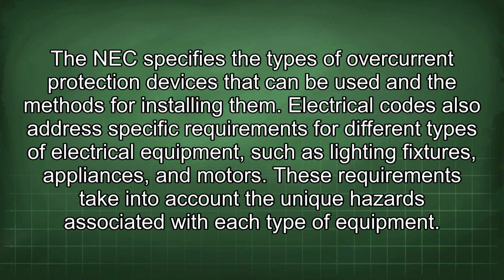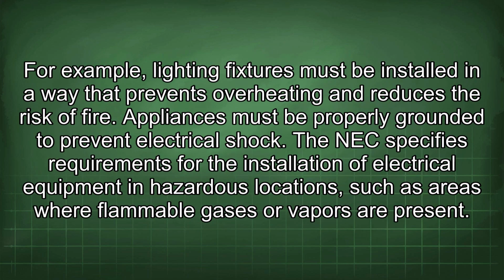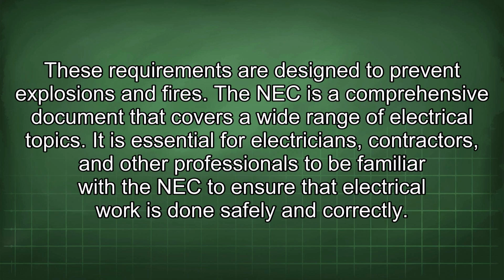them. Electrical codes also address specific requirements for different types of electrical equipment, such as lighting fixtures, appliances, and motors. These requirements take into account the unique hazards associated with each type of equipment. For example, lighting fixtures must be installed in a way that prevents overheating and reduces the risk of fire. Appliances must be properly grounded to prevent electrical shock. The NEC specifies requirements for the installation of electrical equipment in hazardous locations, such as areas where flammable gases or vapors are present. These requirements are designed to prevent explosions and fires.